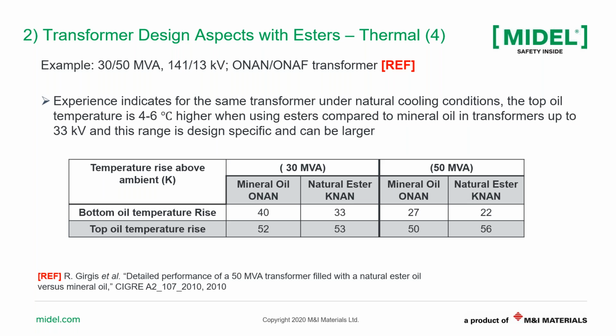The same transformer, now if we increase the loading to 50 MVA, the top oil temperature increased from 50 under mineral oil, as you can see, to 56. So in general, and this will lead us to the next section, which is retrofilling, we expect the top oil temperature with an ester to be 4 to 6 degrees higher than that of a mineral oil for the same design. And I must emphasize here, this really depends on the transformer size, on the transformer loading, on the winding type, as I reviewed in the first slide for the overall performance.